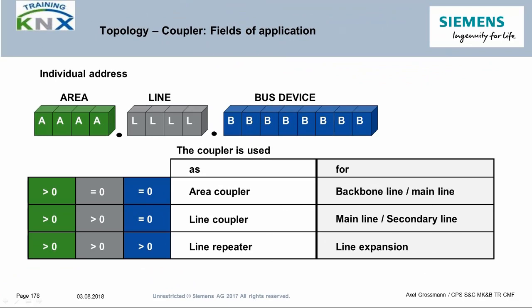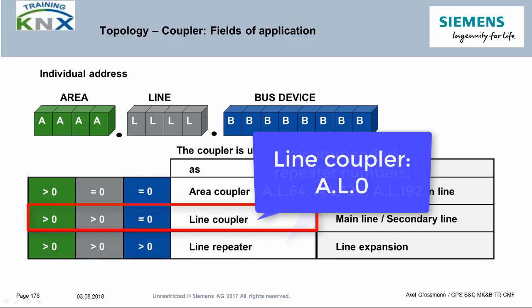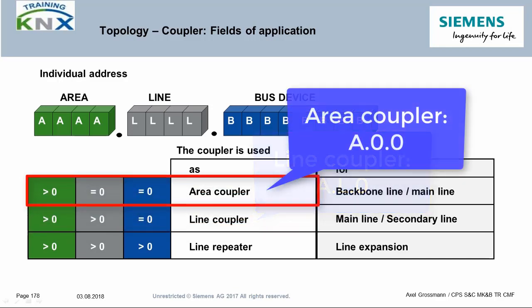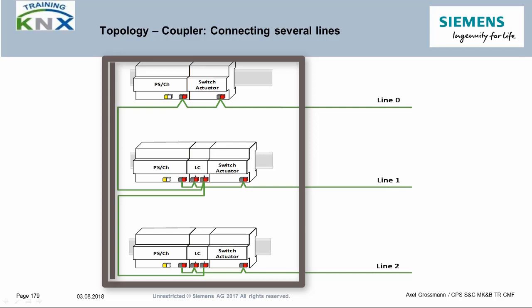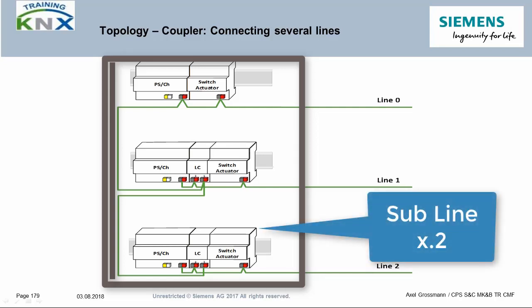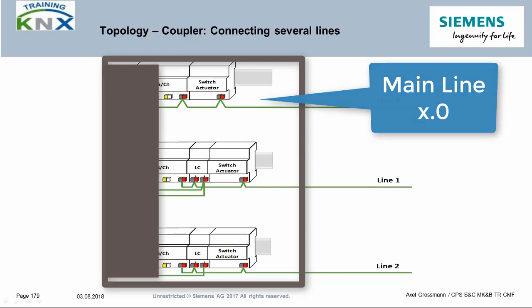To repeat, here again the addressing of the couplers. A line repeater is not different from a normal bus node — all its address components are greater than zero. However, it is recommended to use the numbers 64, 128, and 192 as the subscriber address of a line repeater. Line couplers have the subscriber number zero, a line address greater than zero, and an area address greater than zero. Area couplers also have the device number and the line number zero. Each DIN rail has its own line assignment; all rails are connected in parallel at the terminal of the higher level line of the line coupler.